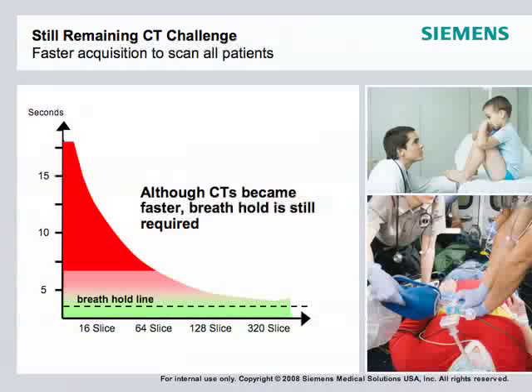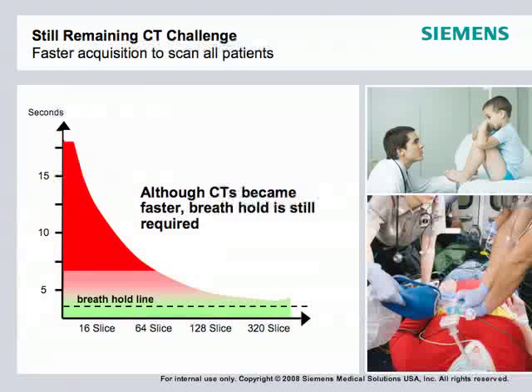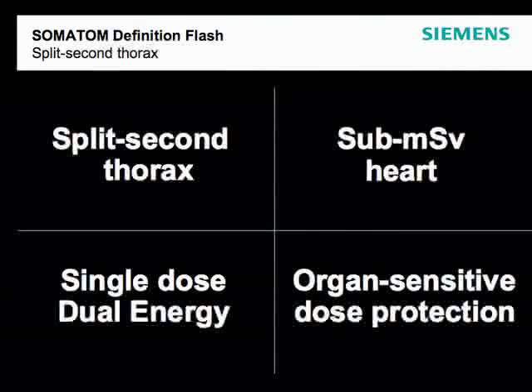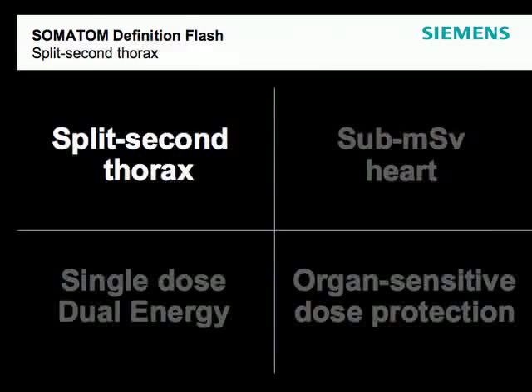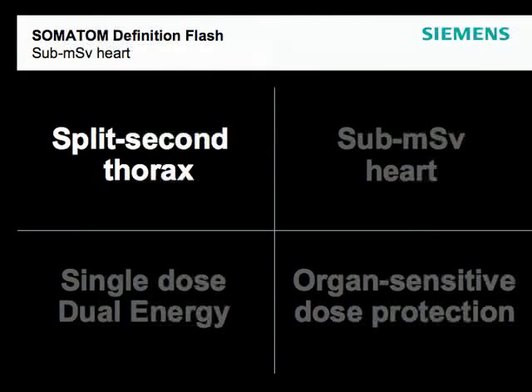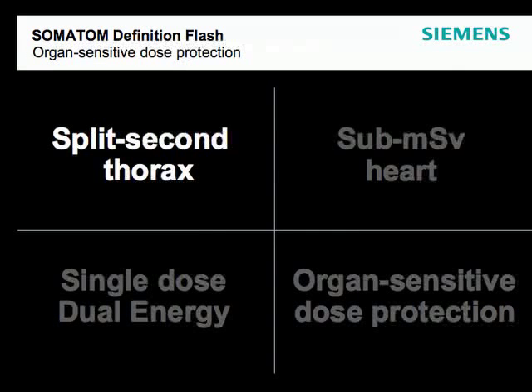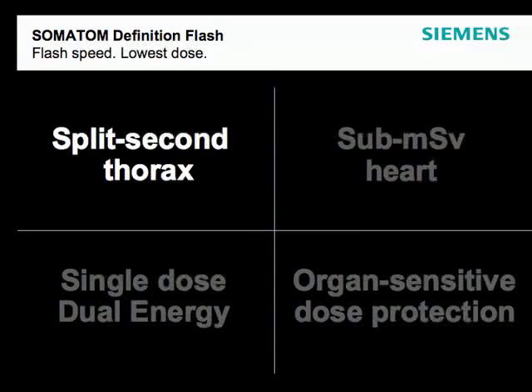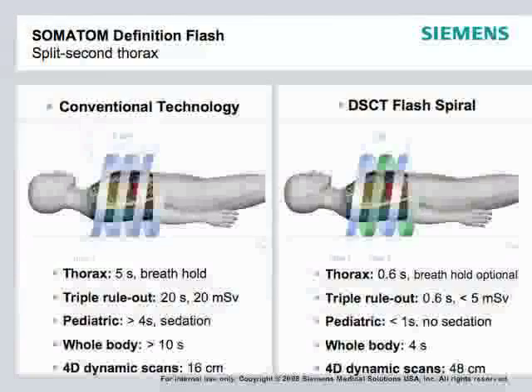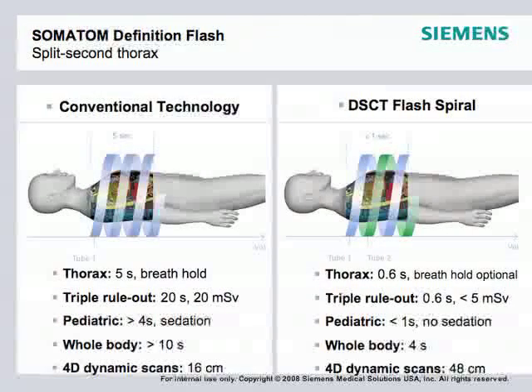Being able to get below the breath-hold line has been a goal as technology develops. For the first time, we're able to achieve a split-second thorax — scanning so rapidly that it can be done without breath hold. Conventional technology can scan an entire chest in about five seconds, but patients with COPD or others who can't hold their breath present a challenge. We can make breath hold optional at 0.6 seconds with split-second thorax.